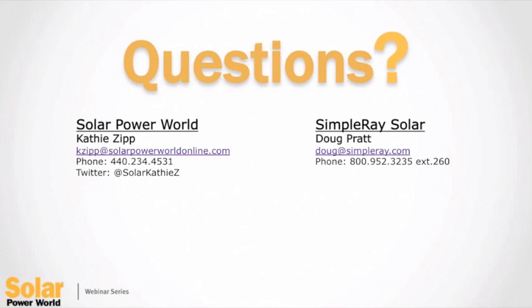Here's a question about the draining of batteries. What's the maximum that the batteries should be drained? Most of these deep cycle batteries that we use for solar can tolerate 80% depth of discharge. That's you're using 80% of the power. You know, there's 20% left. That's about the max, and even that is something you don't want to do any more than you can help.